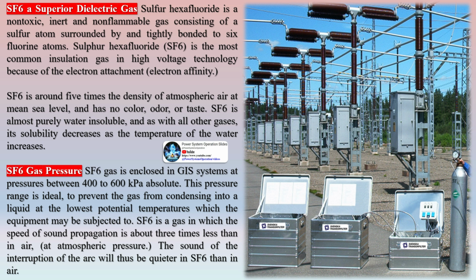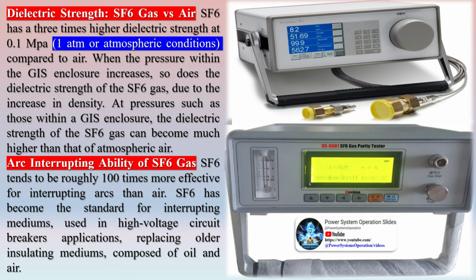SF6 gas is enclosed in GIS systems at pressures between 400 to 600 kilopascals absolute. This pressure range is ideal to prevent the gas from condensing into a liquid at the lowest potential temperatures which the equipment may be subjected to. SF6 is a gas in which the speed of sound propagation is about 3 times less than in air, at atmospheric pressure. The sound of the interruption of the arc will thus be quieter in SF6 than in air.